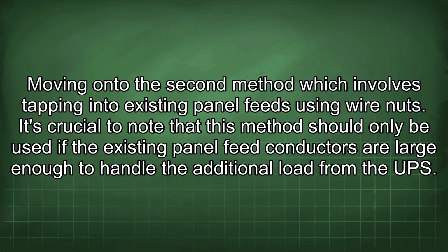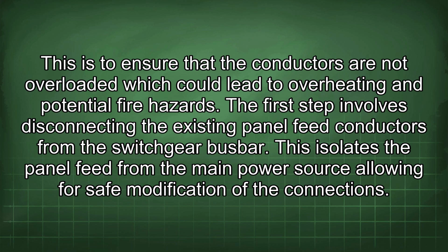It's crucial to note that this method should only be used if the existing panel feed conductors are large enough to handle the additional load from the UPS. This is to ensure that the conductors are not overloaded, which could lead to overheating and potential fire hazard.